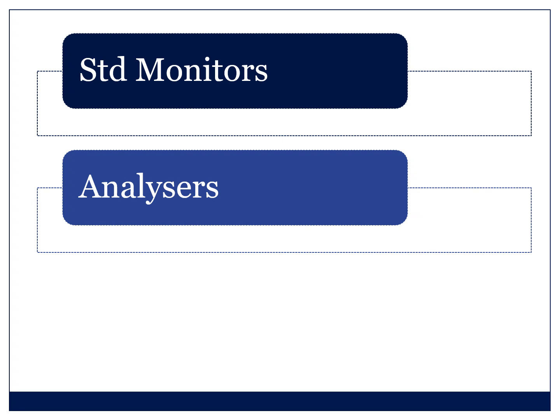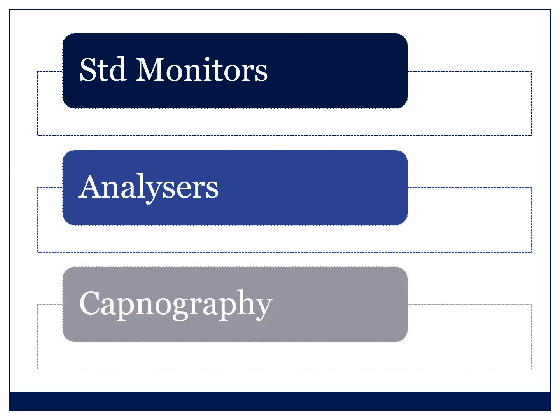So what I normally do is just make sure that when I'm giving room air, I'm getting a reading of 21%, and when I'm using 100% oxygen, I'm getting a reading of 100. So I just check that the thing is calibrated. The actual calibration is specific to the machine. You might need your manual. And then check that you've got capnography and that it's working. You can just take the tubing off the filter and blow into it, and you'll see the CO2 rise on the machine. Then you know you've got working capnography.